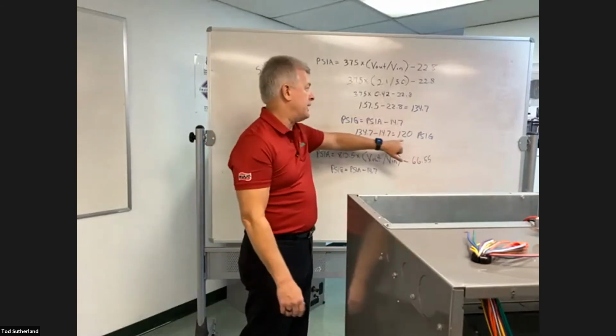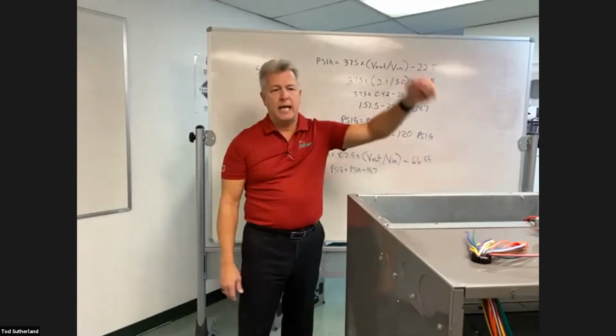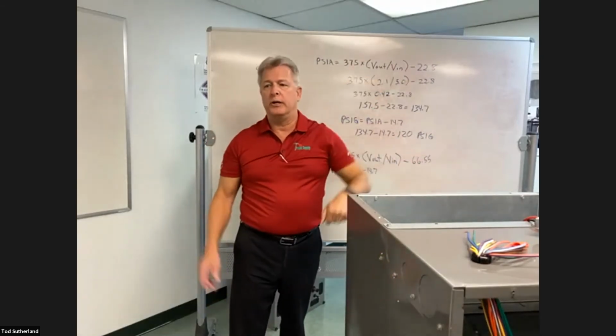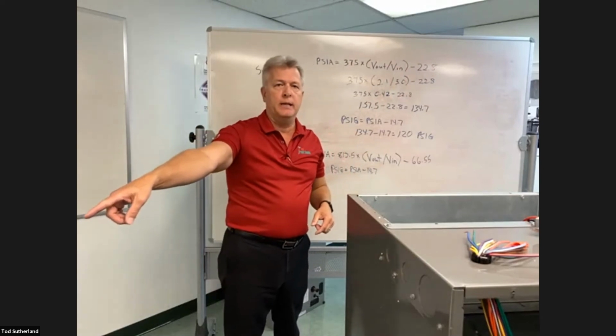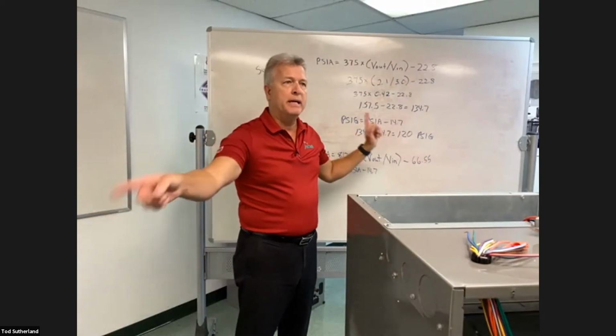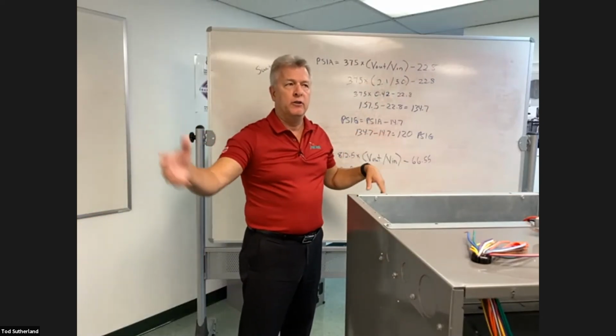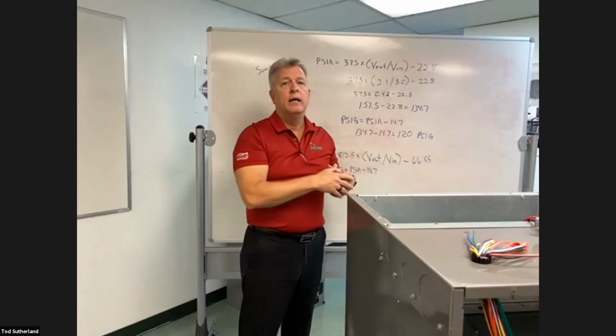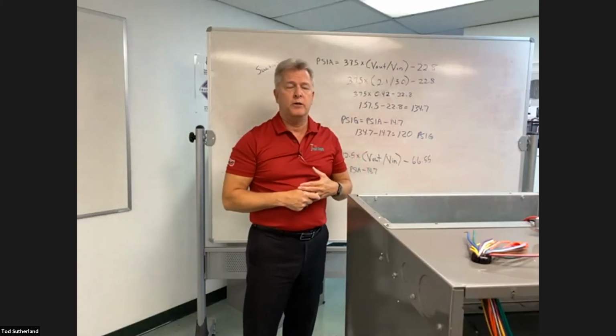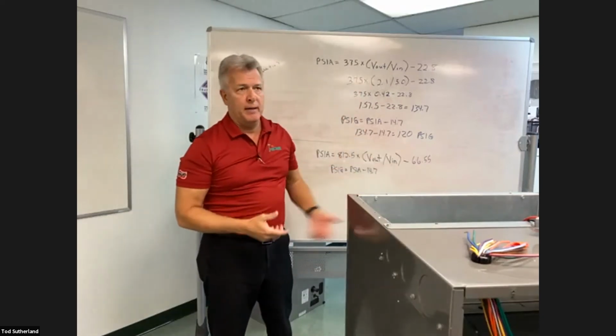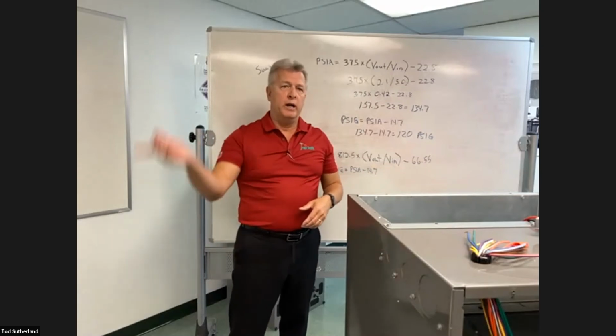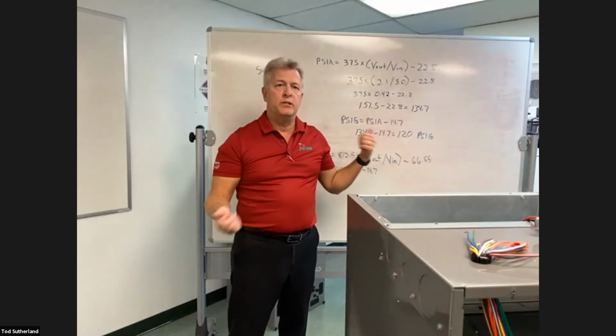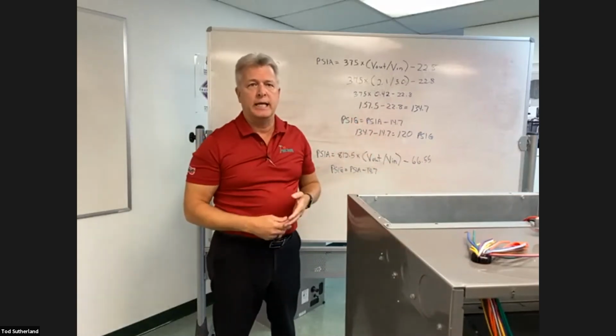Because again, where you're checking this is at the coil here, but your gauge is reading out of the outdoor unit. So there's going to be a difference in that pressure simply because of the line set length and where your line's running through, whether it's running through a chase pipe that might be filled with water or you're running through a hot attic. So there will be some difference that you have to, of course, account for.